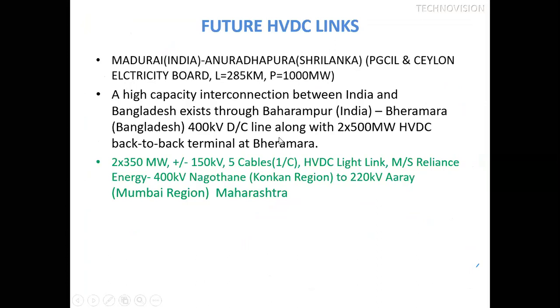Again, we already talked about the India and Bangladesh interconnection along with the 400 kV double circuit line and two 500 megawatt HVDC back-to-back terminal stations. And one link was proposed by Reliance Energy, from 400 kV Nagothane, which is in the Konkan region, to 220 kV Aaray in Mumbai. This was based on voltage source converter technology, because this is also a different technology. It is not a current source converter. These are voltage source converters. But because of some issues, they are not installing this project.